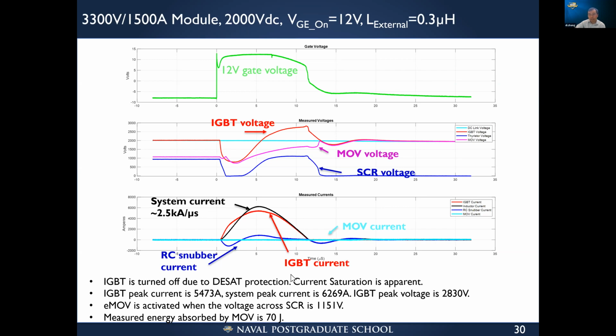However, because the IGBT saturated, right, the current is actually clamped to 5.4 kiloamp. As you can see, it's clamped. If it's not clamped, the current will keep increasing, and probably when we really start to cut it, the current is already definitely more than 10 kiloamp, which will make it super difficult to cut. But now it's limited to about 5.4 kiloamp.